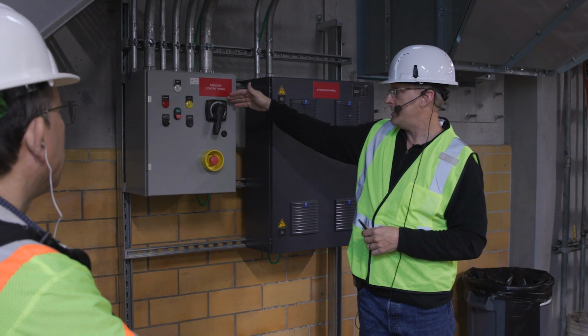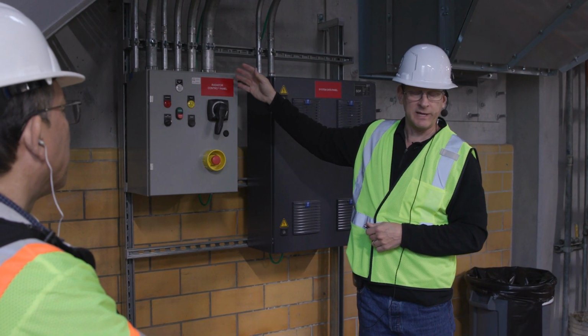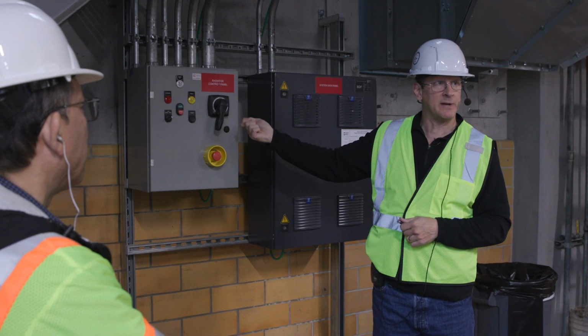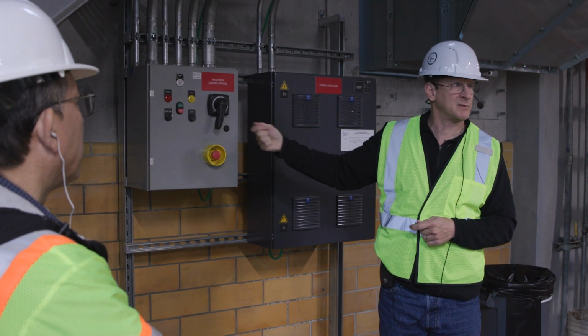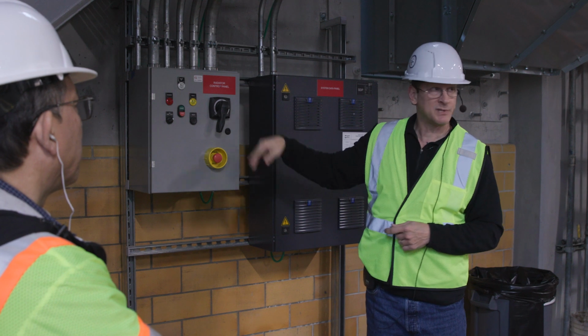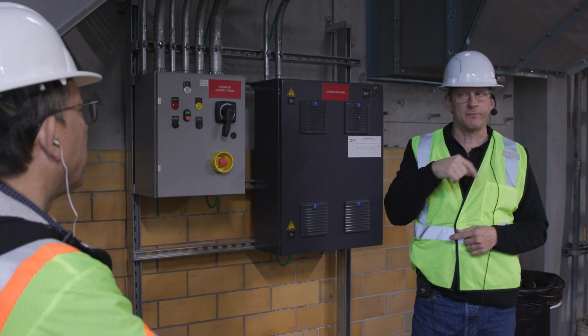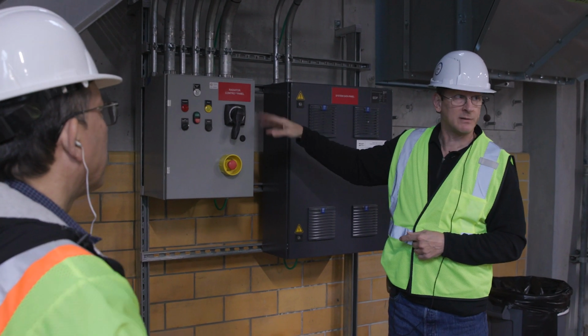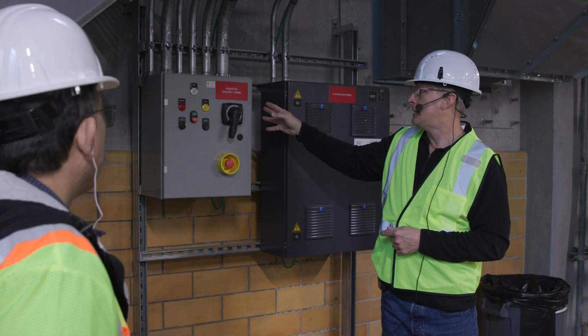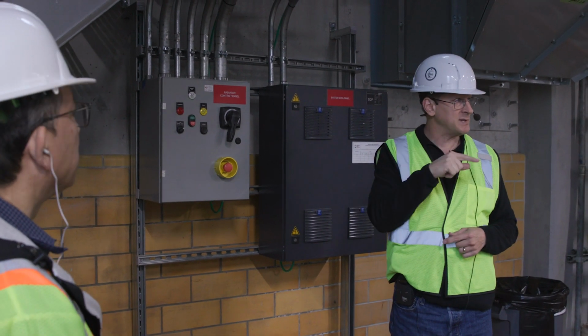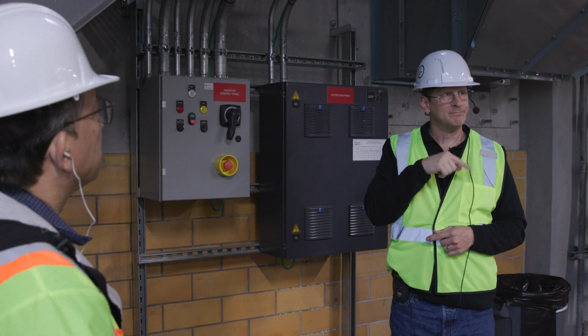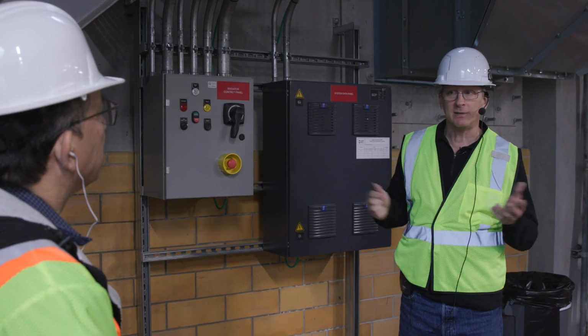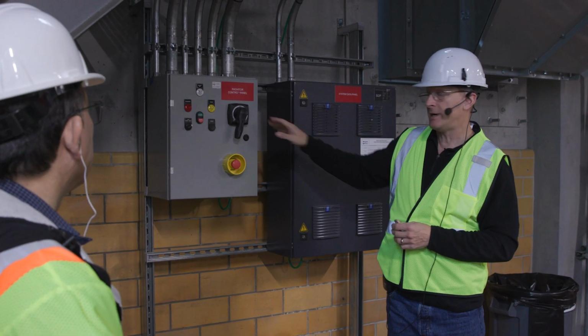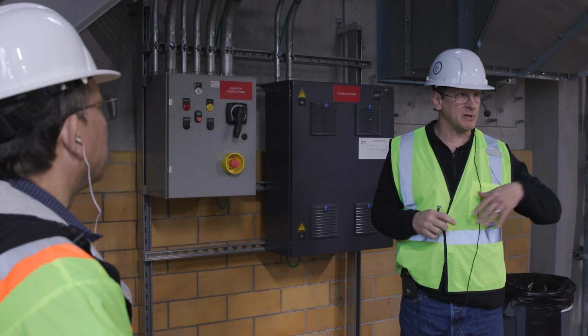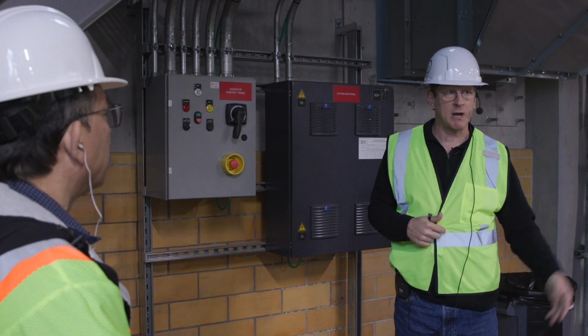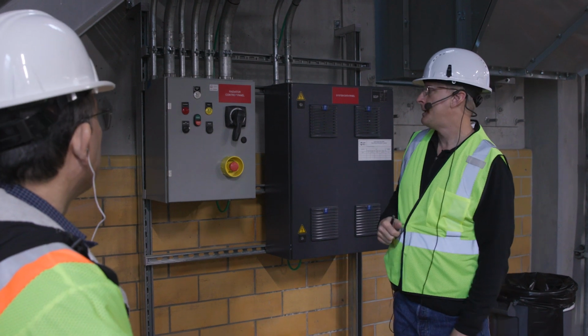We've actually adjusted a delay that we can adjust to automatically clear that fault, and I think we set it for 15 seconds or something. But you might still see it at the UCP, but that's only for a first start initialization. After that, you won't see it. I might have to change the program to put a timer on that at the UCP as well. But this should clear itself. That alarm might still stay active, so you might have to clear it at the UCP. We'll probably see that tomorrow when we start it up.